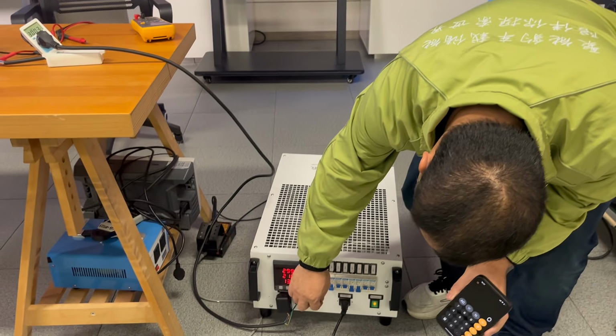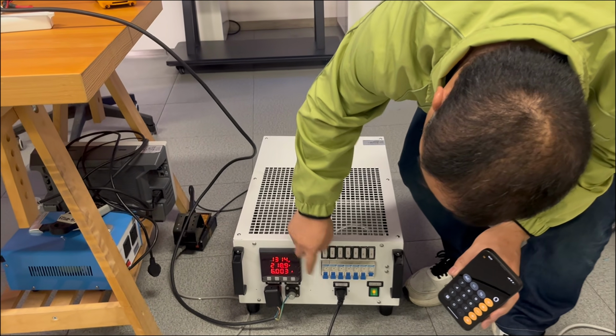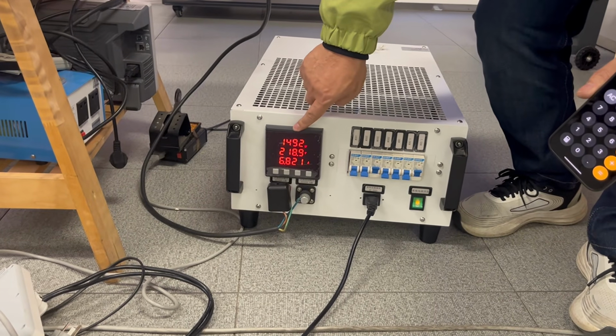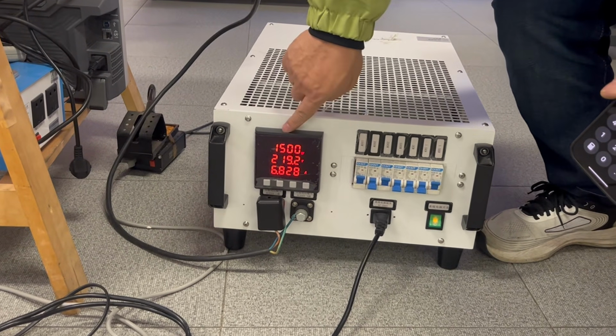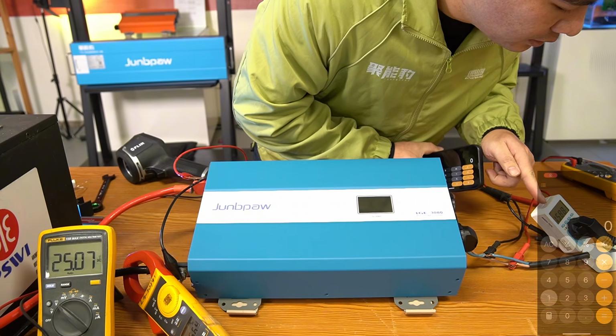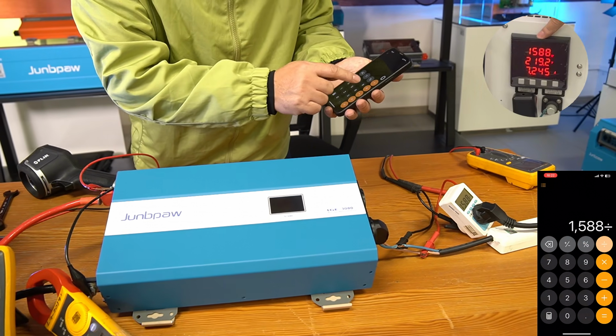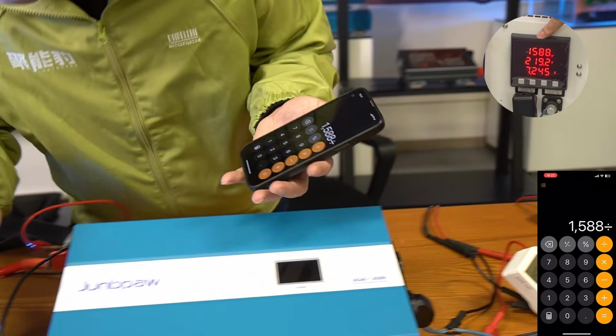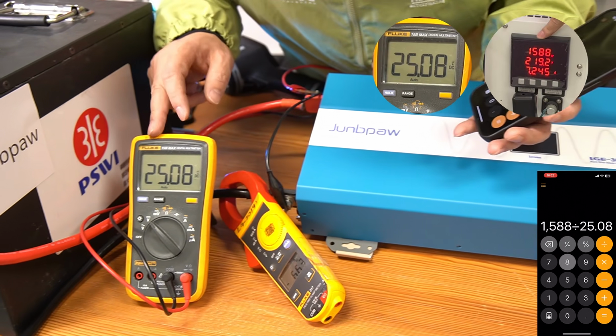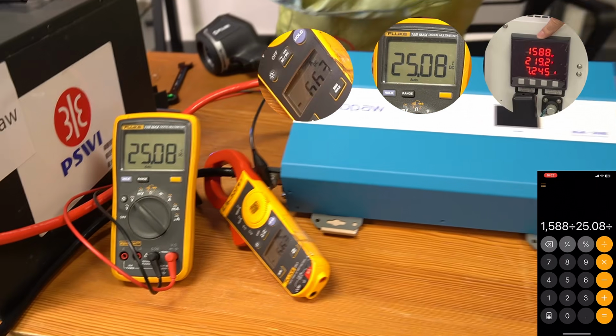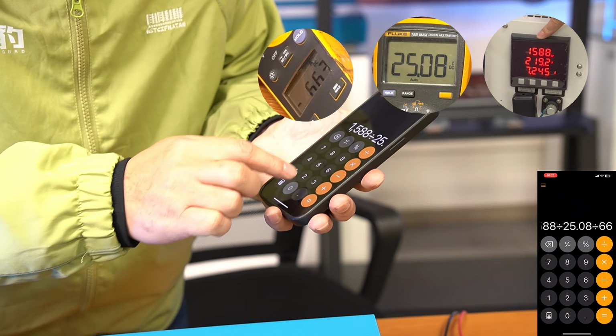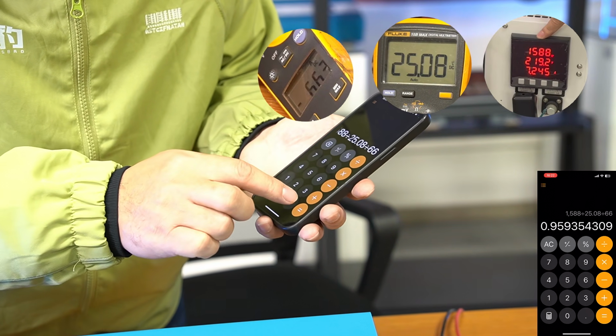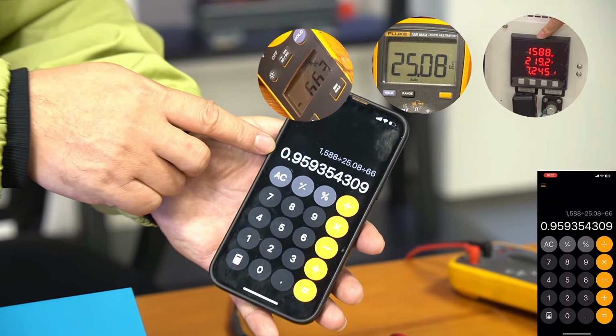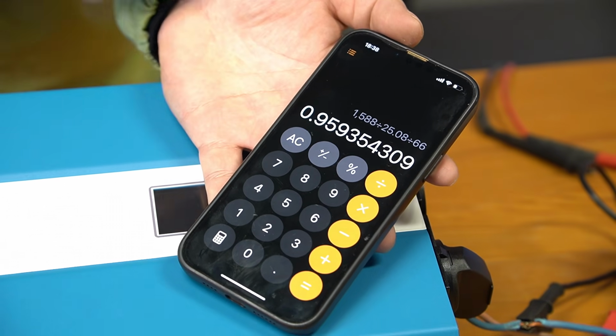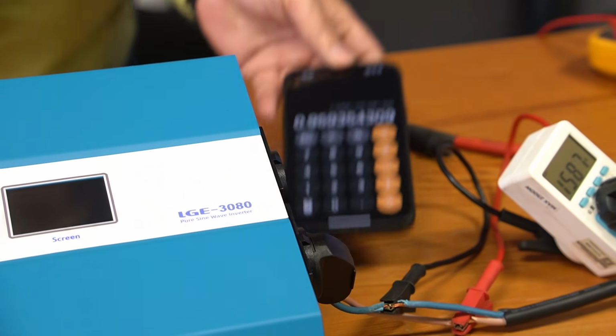Next, we'll adjust the load to around 1500 watts, which is approximately half load, to see how the efficiency changes. Alright, the load is now stabilized at 1588 watts. We'll use the same formula to calculate. 1588, 25.08, 66. The result is 0.959, meaning 95.9%. This is its working efficiency at half load, reaching 95.9%.